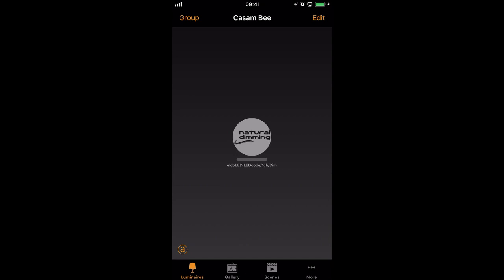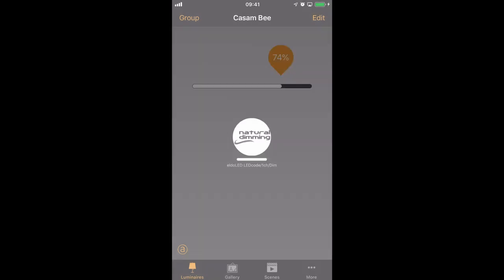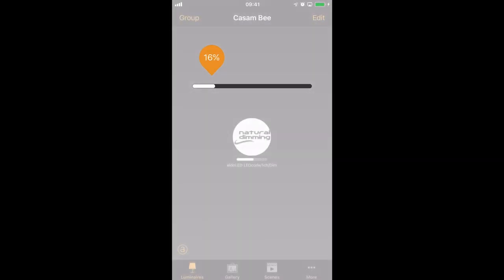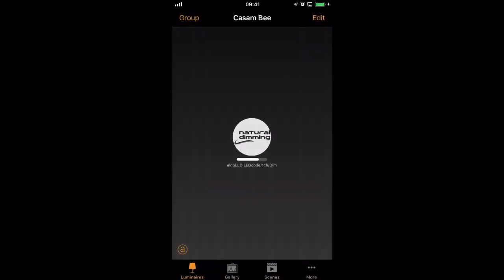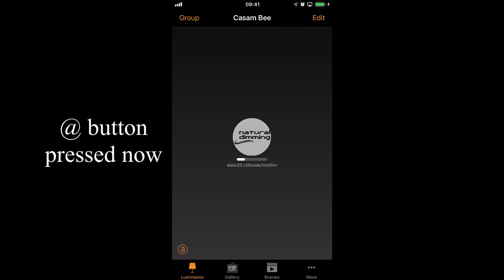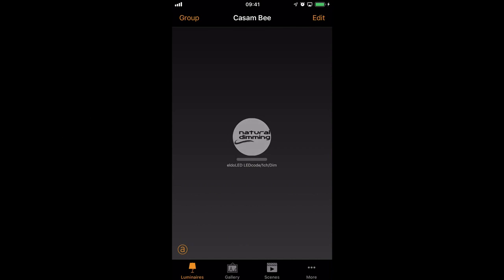You'll notice that I've previously used the A button at the bottom left hand corner for automation. Pressing that button will automatically resume automation for everything in the entire network. Although I only have one luminaire here, if I manually control it up and down, select automation. If I select automation, it removes manual control and turns the light off, because nothing is triggering or nothing is automating that light right now.